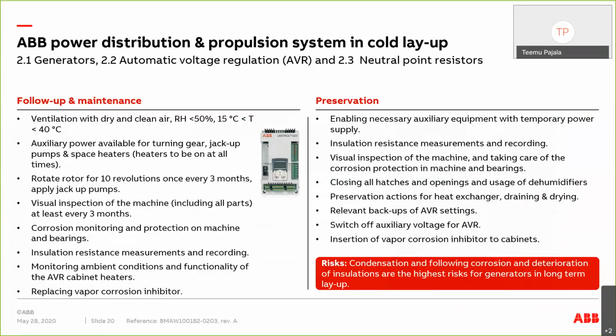And then it's good to make insulation resistance measurements every now and then to keep track of the condition of the winding, especially if there are problems with the temperature or humidity on board. Then it's more important to keep track of the level of insulation in the winding. And then vapor corrosion inhibitors inside the cabinets need to be replaced when they're getting old. That's mainly for the AVRs.